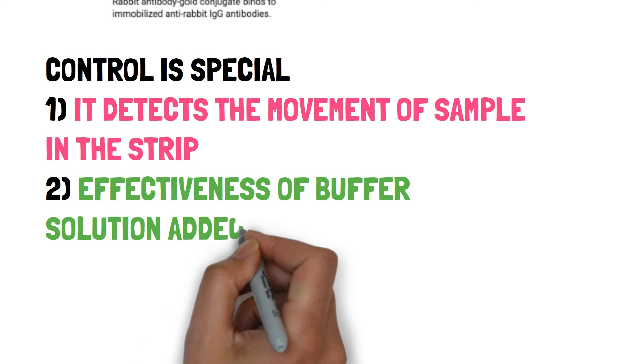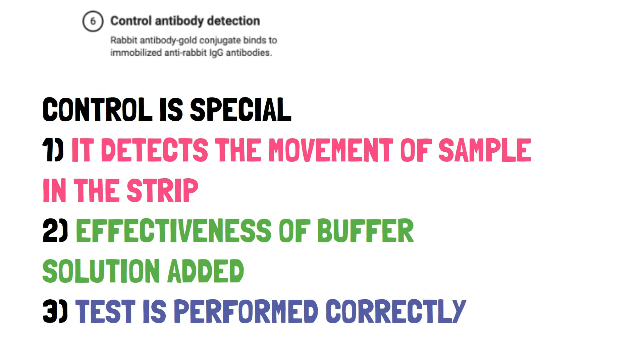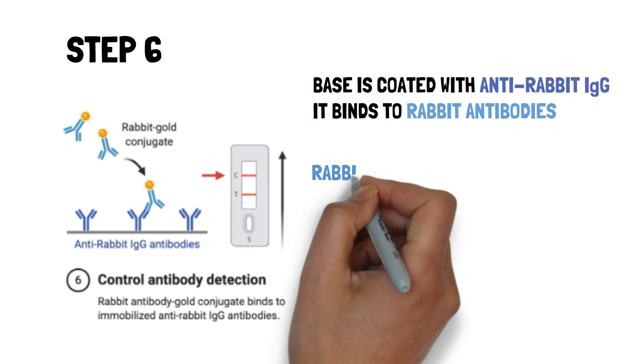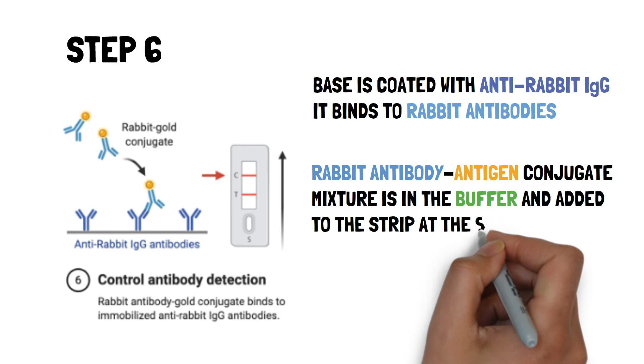It tests the movement of the sample in the strip, also the effectiveness of the buffer solution added, and it also checks if the test is performed correctly. So when we see a control mark, only then we can say that the test is valid. As you can see here, on the control surface there are anti-rabbit antibodies lined up on the strip, which are immobilized and fixed here, and inside the strip there are preloaded rabbit antibodies that are gold coated. So whenever these gold-coated rabbit antibodies reach the control area, they are captured by the anti-rabbit antibodies and are stuck there. This results in the formation of a mark or a line on the control region.